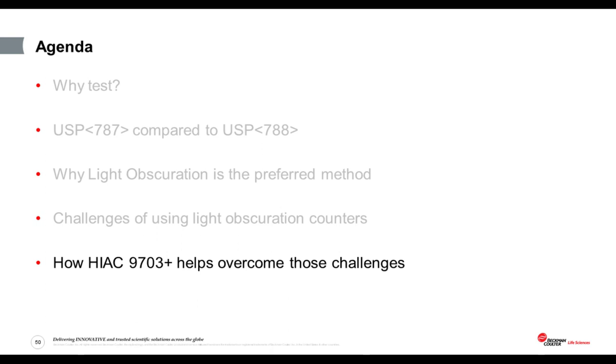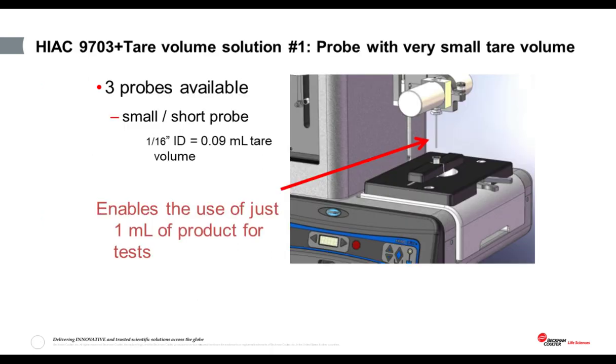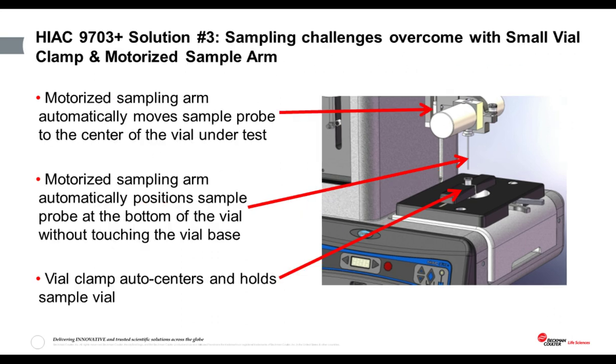Okay, coming into the last section of our talk today. So let's take a look at how the HIAC 9703 Plus from Beckman Coulter helps users overcome these challenges. Well, firstly, the HIAC 9703 Plus gets around the tare volume problems by having a probe specifically designed to enable USP 787 testing, which has a tare volume of just 0.09 milliliters. Now, this should allow the user to perform USP 787 using just 1 milliliter of product.